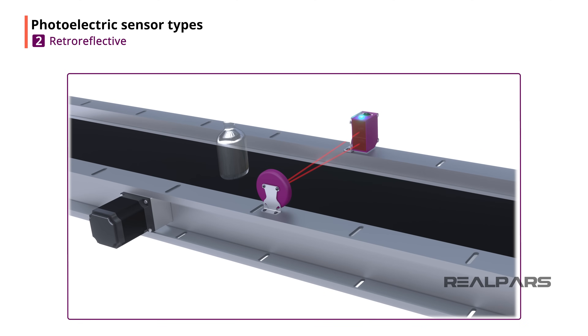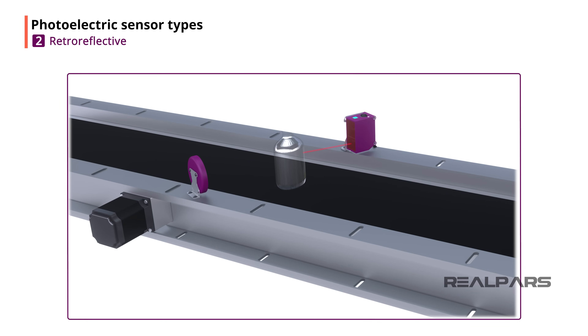Some disadvantages of using a retro-reflective sensor are: you have to install the sensor with a reflector; if the object is shiny, it might turn on the sensor's output instead of the reflector; and the light beam is not as focused as a through-beam sensor's light beam. If the object is shiny, you can try adjusting the angle of the sensor and reflector compared to the object.